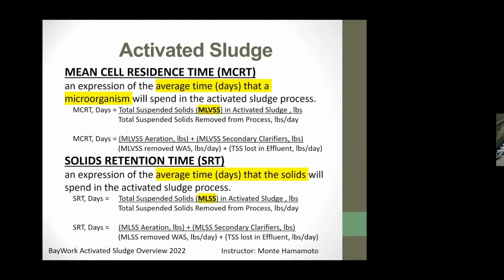When that happens, you start to denitrify, you start to do a lot of other things, and that added to the increase in turbidity. What we did, we took 2 clarifiers out of service, and that's our summer operation. That will balance it, getting our hydraulic retention time back up where it needs to be within our target, and also our solids retention time. But we have to readjust the RAS when we do that. So it's very important to look at these parameters and have them in your process control programs.